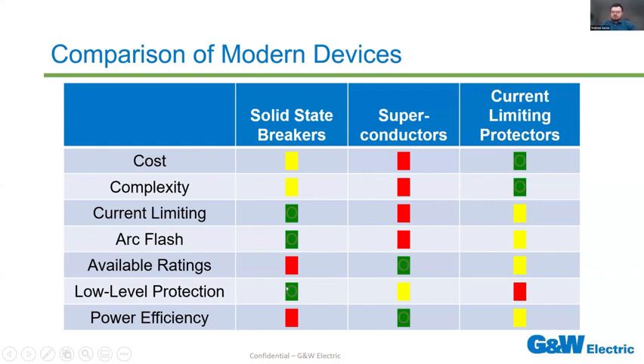In terms of low-level protection, solid state breakers are once again going to be the best. They clear that fault instantly. Superconductors are in second, while current limiting protectors will come in last, as once again, they are not a low-level fault protection device. They're only going to operate and clear that fault in your worst-case fault scenario. So that is a trade-off in order to limit the amount of nuisance tripping from your current limiting device.